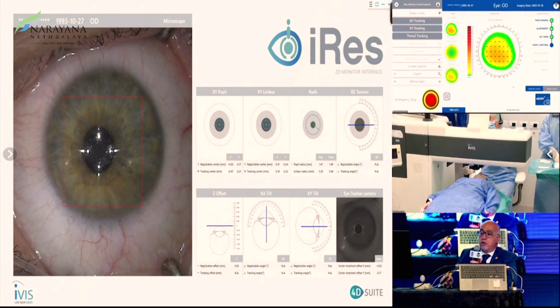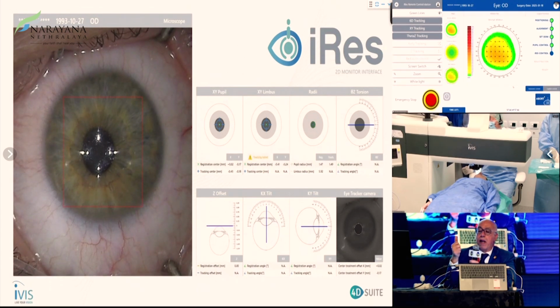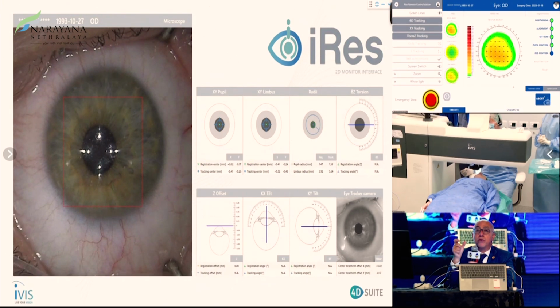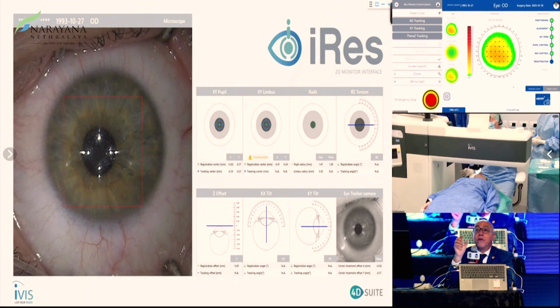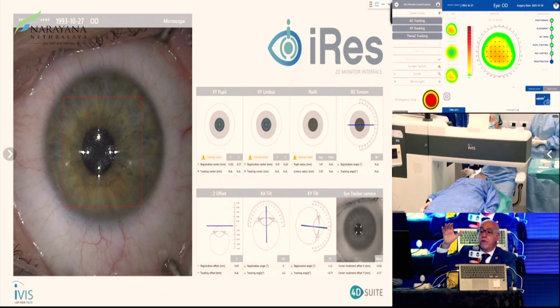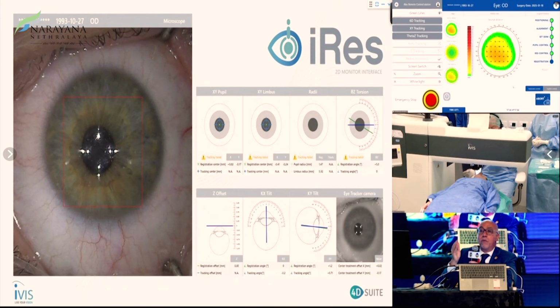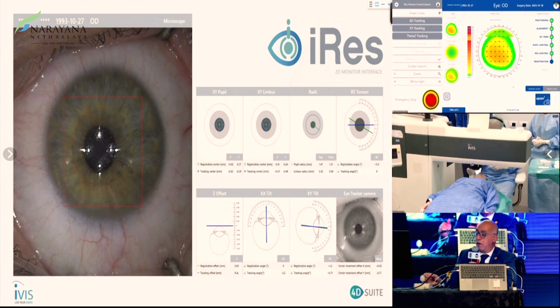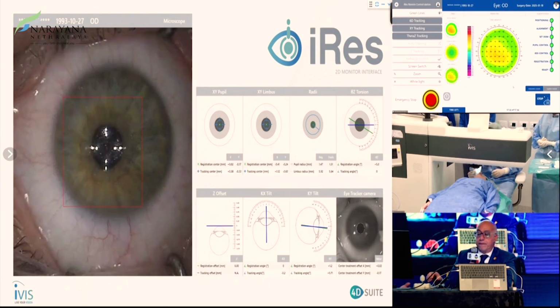After drying of the cornea, I will press the button to execute the treatment, after taking care that all the checklists are signed with a green sign. So we have passed from the positioning to the alignment, to the application of the dome, which is the cone, to the pupil control, which brings the pupil to the exact size, to the iris control, which is an iris pattern registration, and then the full registration of the eye. And then when it is ready, I can press the button and execute the treatment.